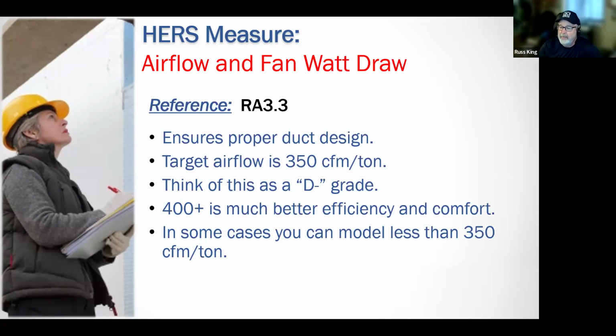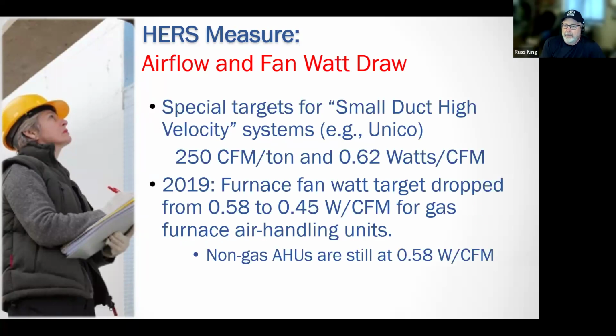All right. It's a very low bar. Let me put it that way. It's a very low bar. In some cases, you can model less than 350 CFM per ton. There's some extra things you can do with zonal control where it'll actually allow you to have less than 350. That's not a good system, but again, it's the worst system you're legally allowed to build. All right, if it just barely passes code. So small duct high velocity systems, Unico, SpacePak, those kinds of systems, they have their own targets. They're different because it's a different kind of system.